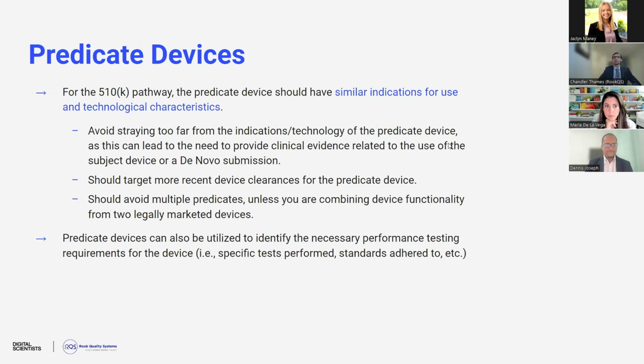So when we say predicate devices, these are similar devices in terms of both indications for use and technological characteristics. Of course, no two devices are exactly the same, so there will be differences, and that's part of what FDA is going to review, to make sure that any differences between your device and the predicate device have appropriate justifications and supporting data to show that they don't impact that substantial equivalence determination.